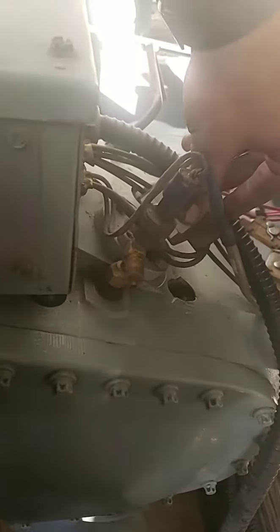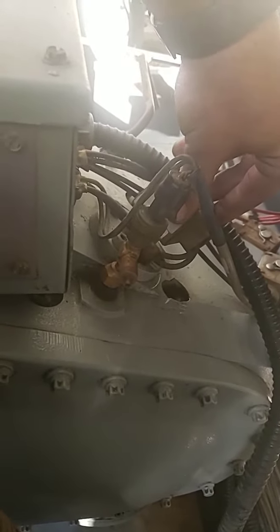So we'll get a top side view. I hope you guys can see that. We'll come around over here. There we go. So this is your oil pressure transducer. So it's reading right off of the oil input side of the system. This is your oil valve. Got a little solenoid on it. It's literally just a solenoid actuated valve. That's all it is. But it's how the compressor can control its oil flow. And so this little Schrader here, my finger's on, that is your oil port coming right off the compressor. This goes into the filter housing.